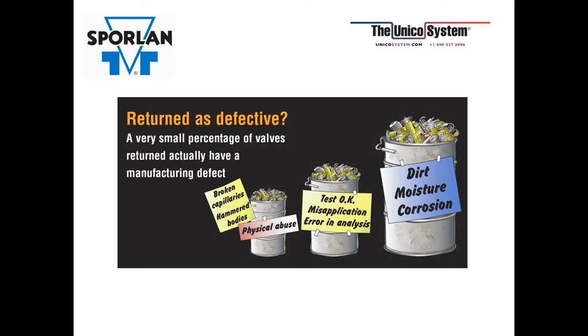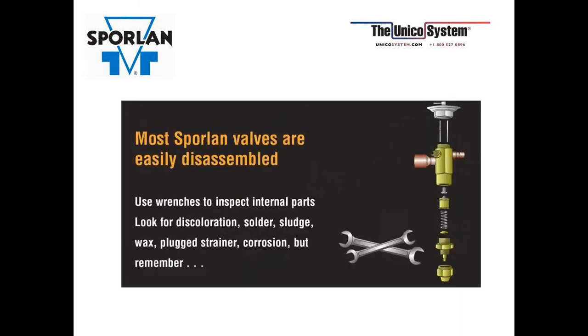And then our biggest culprit for issues is the dirt, moisture, and corrosion in the valve. And that goes back to proper charging and evacuation of the system. Exactly. But most valves can be disassembled using some wrenches, and you can inspect the internal parts. What you're looking for is discoloration, solder, sludge, wax, any kind of corrosion.